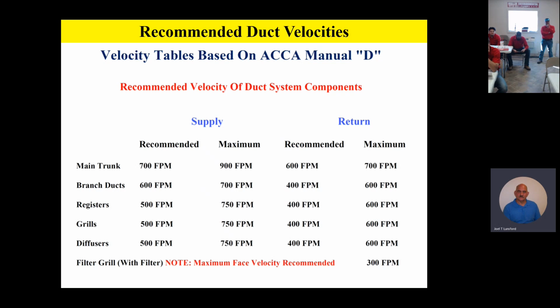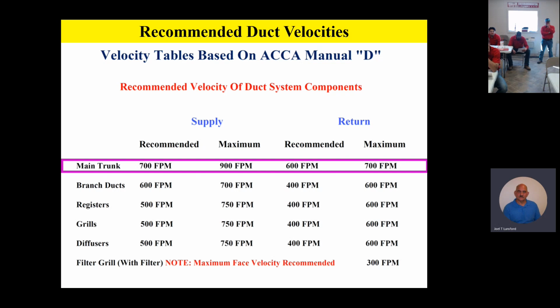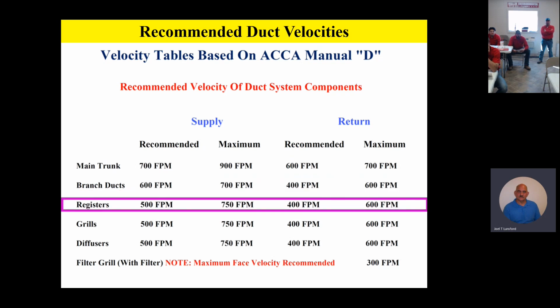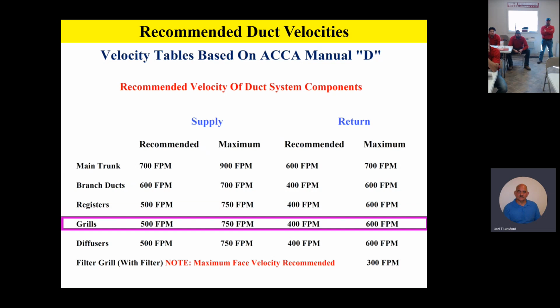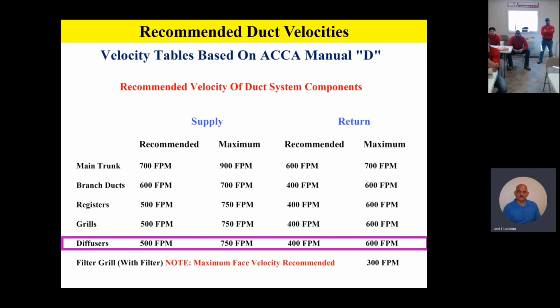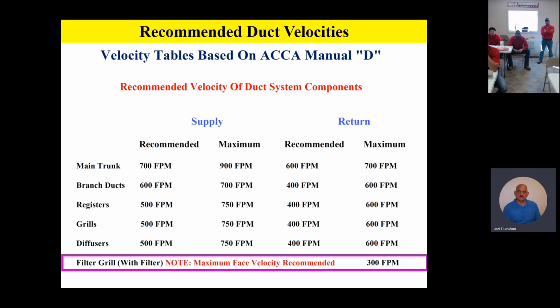Again, a quick reminder that when you're designing a duct system, make sure and really look at this Manual D velocity table, because velocity is a very important consideration when you're taking a look at airflow. If the air is going too fast, it's going to be noisy. In addition, if it's going too fast, the heat exchangers aren't going to be able to exchange that heat properly. So we recommend that you follow these velocity tables whenever you're designing a duct system. And please remember, if you have a filter on or behind a filter grill, do not exceed 300 feet a minute velocity across that filter. That's a Manual D recommendation.